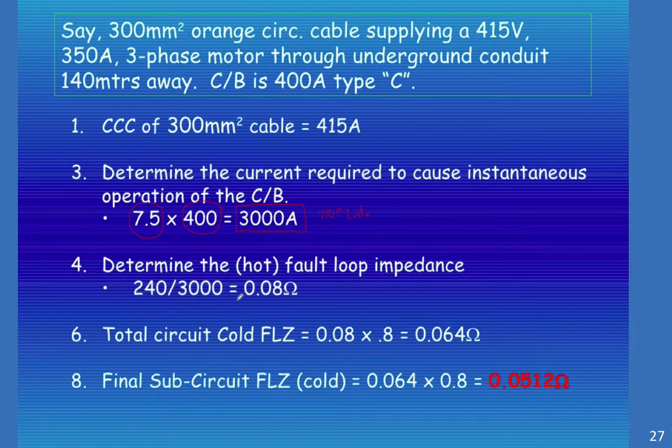Determine the fault loop impedance. If we look at one leg, that's 240 volts phase voltage. Divide that by 3000, we get 0.08 ohms. So the total cold fault level impedance (FLZ) is 0.08 × 0.8 = 0.064Ω.